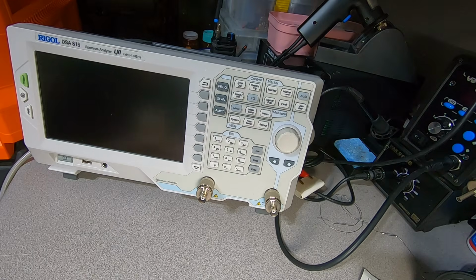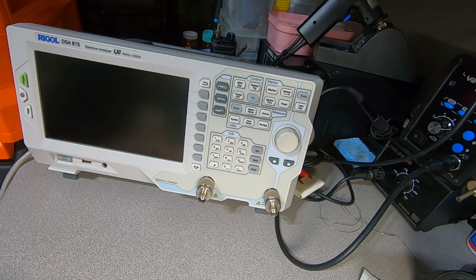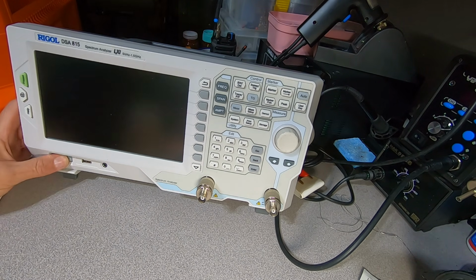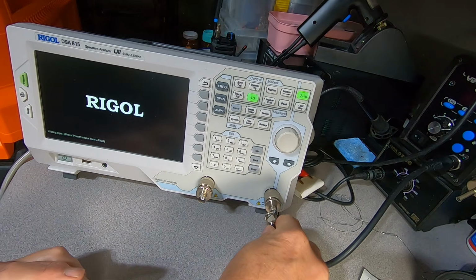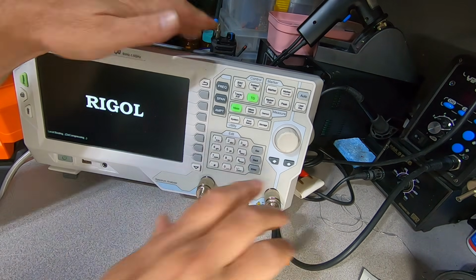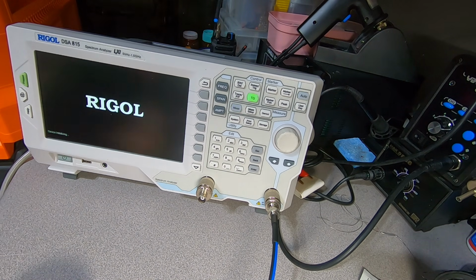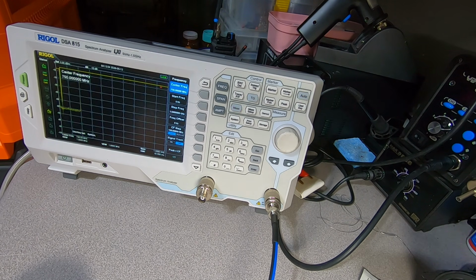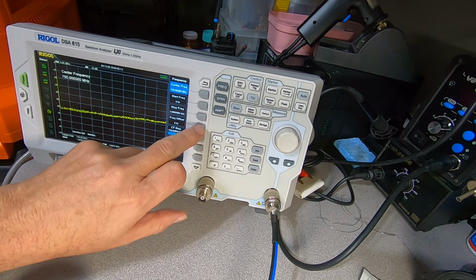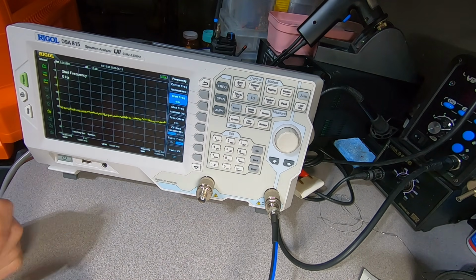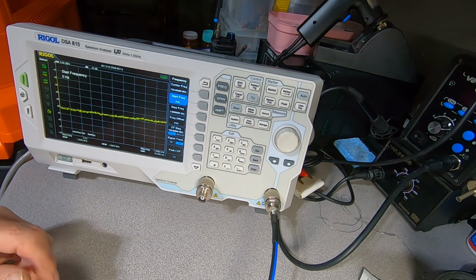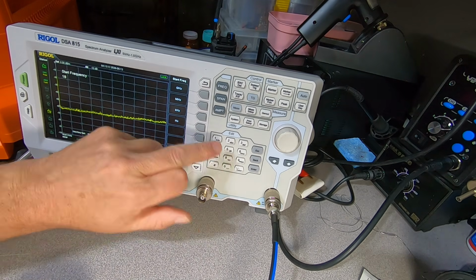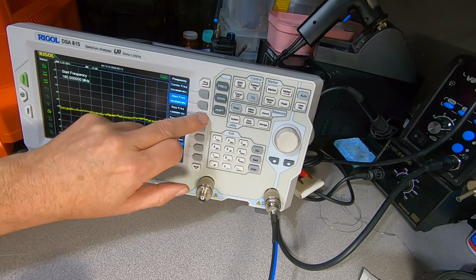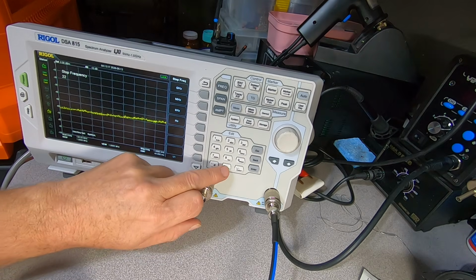Let's configure our spectrum analyzer for configuration 1. Power up your instrument. Hook up your probe. Of course, you want to let your instrument warm up for at least 15 minutes before performing any kind of tests. Go ahead and select your frequency. So let's say we're going to sweep 200 megahertz. We'll start at 180 and we'll stop at 220.